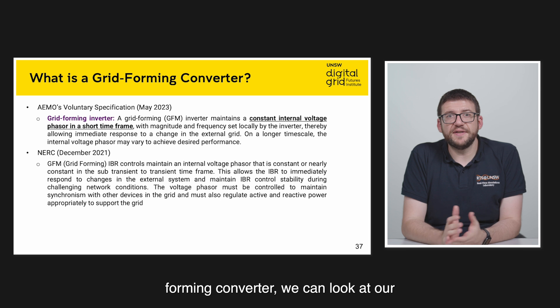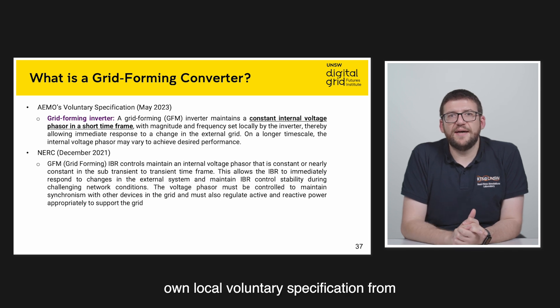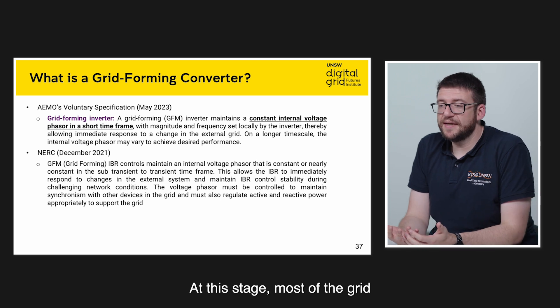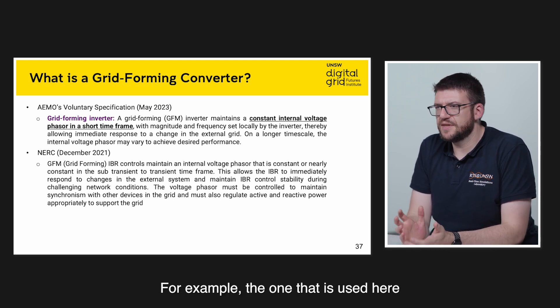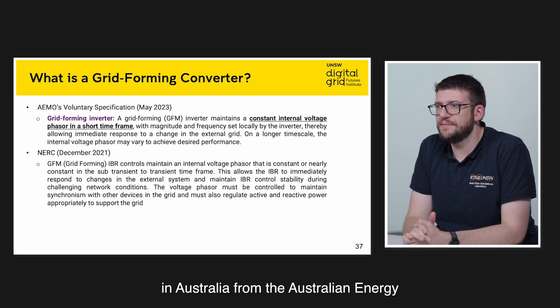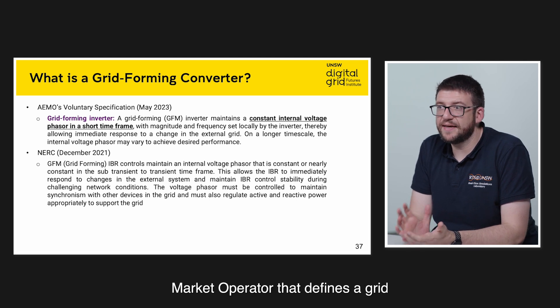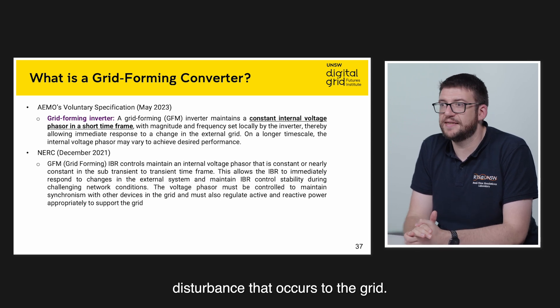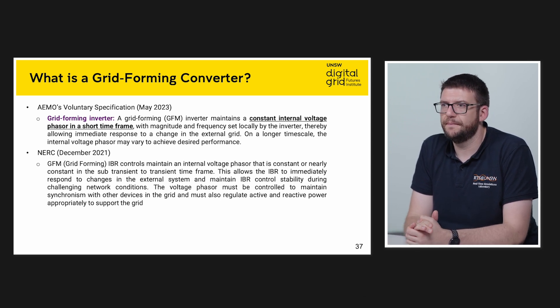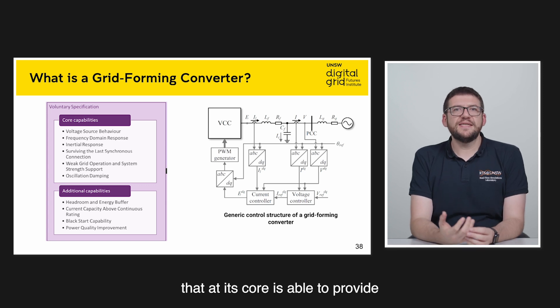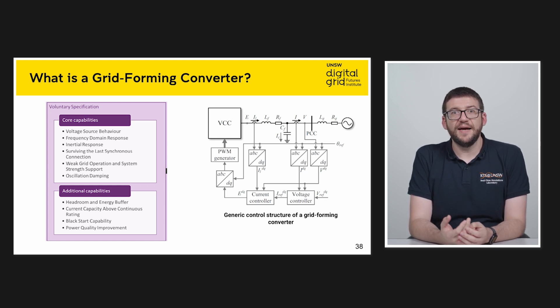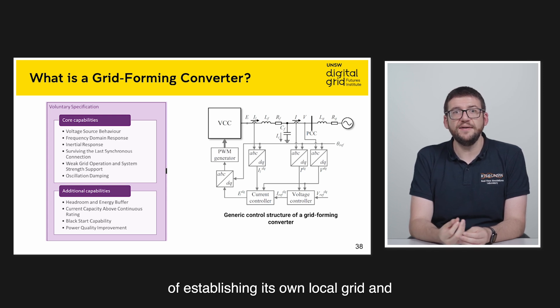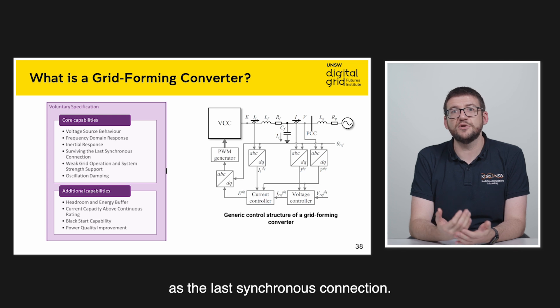In terms of definitions of a grid-forming converter, we can look at our own local voluntary specification from the Australian Energy Market Operator. Most of the grid-forming definitions are voluntary. The Australian Energy Market Operator defines a grid-forming inverter as one that is capable of maintaining a constant internal voltage for a short time following any disturbance that occurs to the grid. This control structure at its core is able to provide frequency and inertial response. As it does not require an external grid to synchronize to, it is capable of establishing its own local grid and maintaining grid synchronization, even as the last synchronous connection.